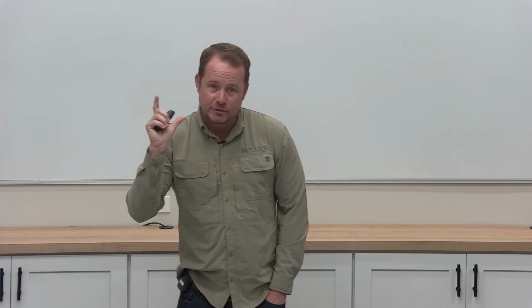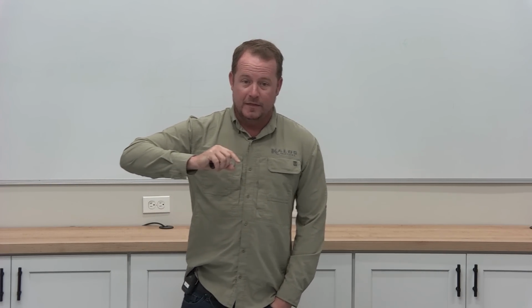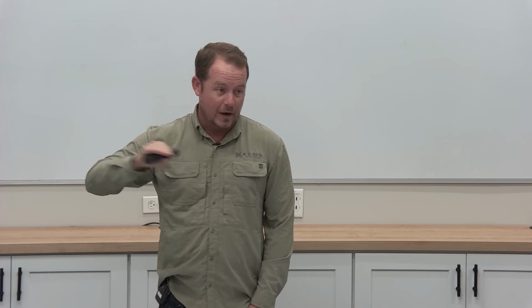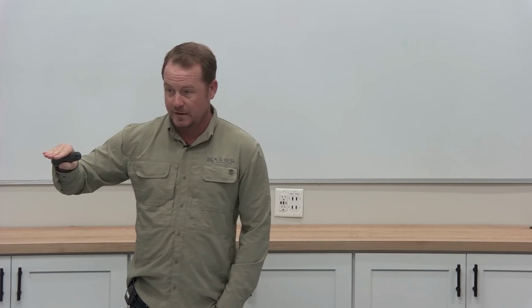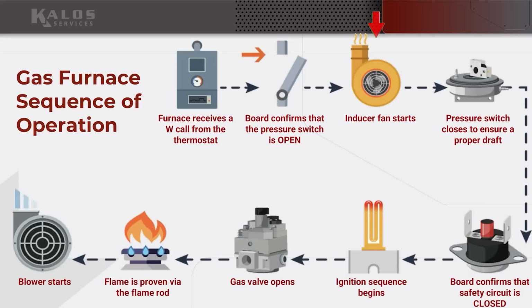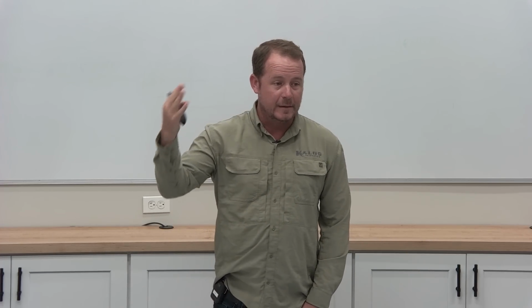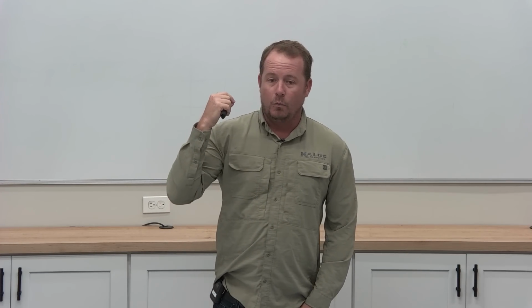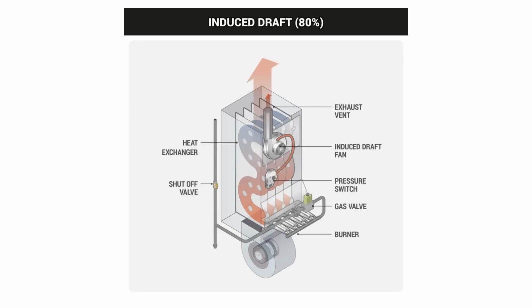If for some reason that switch is closed to begin with, then the board's going to fault out and say, no bueno, that inducer fan was not on, it should not have been closed yet. Does that make sense? That's what the board's looking for there. Then your inducer fan starts. One quick, very important fact, if you get a little deeper into this, what do you think the pressure is in the flue pipe once the inducer fan starts?